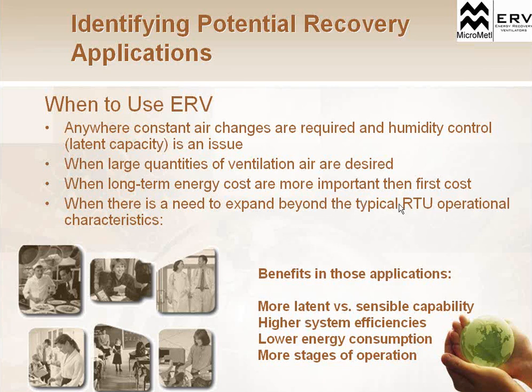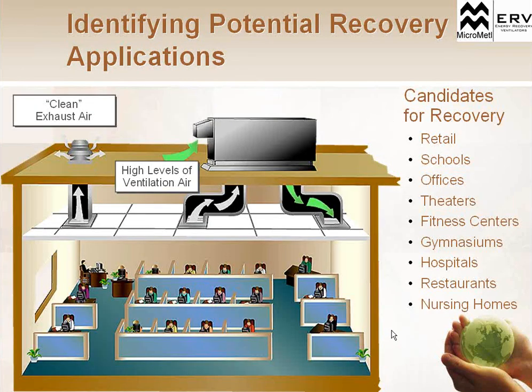When there's a need to expand beyond a typical rooftop operation. Because rooftop units typically aren't sized to bring in 100% outside air, they're sized to bring in 10 to 15% outside air. So when we're able to cut down on that ambient load, that ambient temperature, and that humidity, we can actually use a rooftop unit where we may not have previously done that. So we get benefits of more latent and sensible capabilities. We have higher efficiencies, lower energy consumption, and more stages of operation from that rooftop system because we can size it properly for the actual space, and we'll get better humidification control.